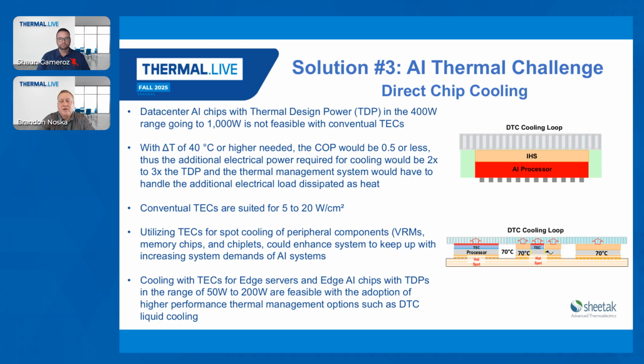As these AI chips get very hot, there's very local heat—your VRM modules, your high bandwidth memory close to the modules, will overheat and sometimes throttle back because they're limited in what they can deliver to the demands of the AI chip itself. This is where a hybrid approach, putting a TEC chip alongside a liquid cooling system, lets us locally control these hot spots or other modules, enabling the VRMs or HBMs to keep up with the demands of the AI chip and maintain temperatures within their operating parameters.